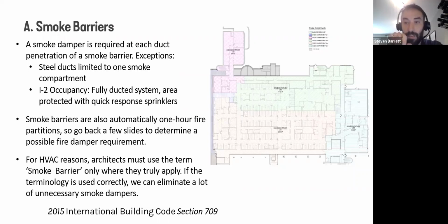So it might be hard to see because it's pretty small here on the right, but that's a smoke compartmentation plan. So there's 4 colors, 4 kind of shapes. On the bottom, kind of an orange tan shape, a green one sort of in the middle top, cyan on the right, and then pink in the upper part. So this floor plan is split into 4 compartments. So unless one of those exceptions are met, anytime a duct crosses that smoke barrier, it requires a smoke damper.